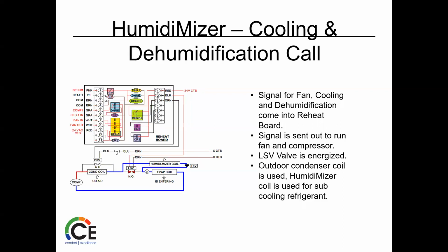So you can have both. You get a signal for cooling and dehum. Signal sent out, runs fan and compressor. LSV is energized. Outer condenser coil is used at this point because we have a cooling call. HumidiMizer coil is used for subcooling refrigerant, so they work together. And you can effectively do both now.